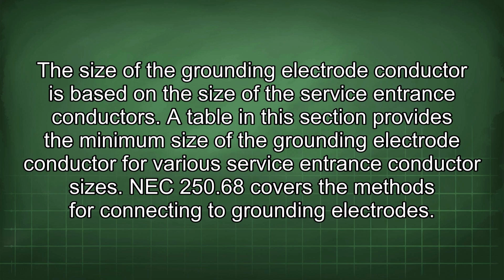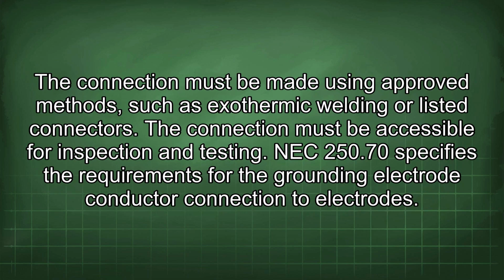NEC 250.68 covers the methods for connecting to grounding electrodes. The connection must be made using approved methods such as exothermic welding or listed connectors. The connection must be accessible for inspection and testing.